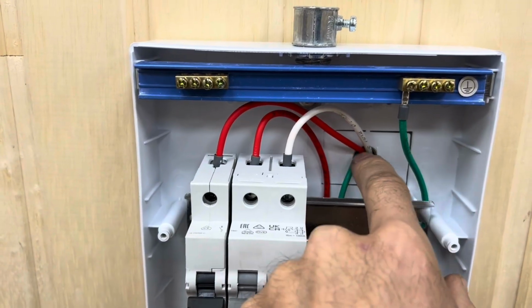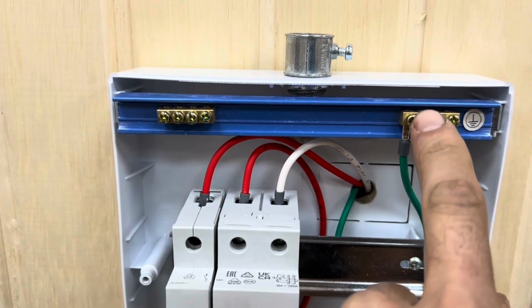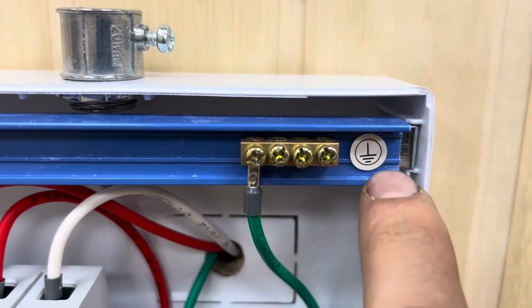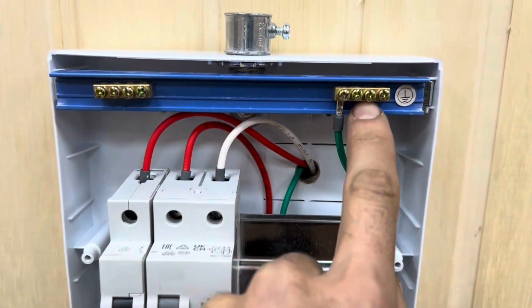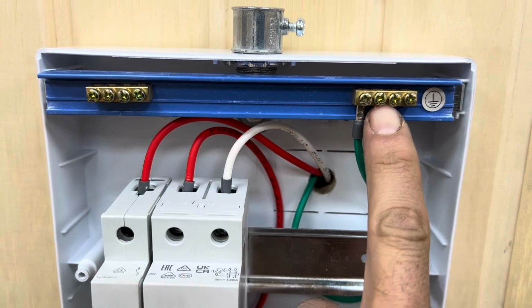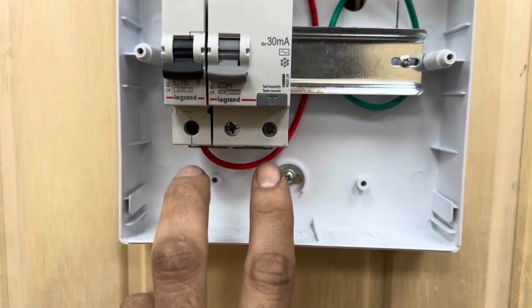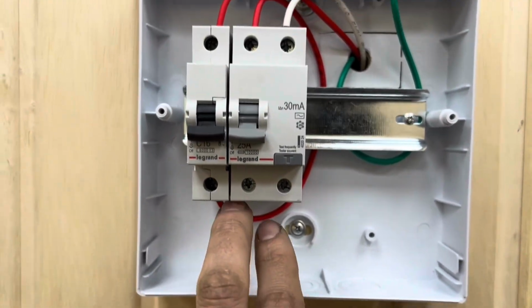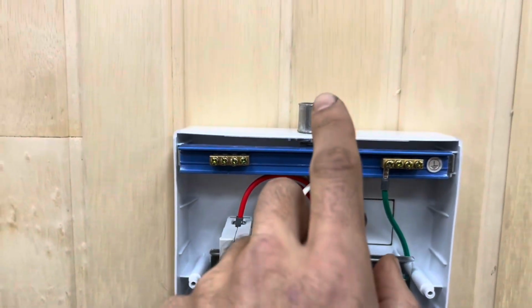The neutral simply enters through the differential, comes out of the differential, and connects to the outlet circuit. The ground comes from the house and connects directly to this terminal that has the ground symbol on it. Then we take another ground from here, from the screw next to it, and it joins with these two that already came out of the breaker, the phase, the neutral, and the ground.